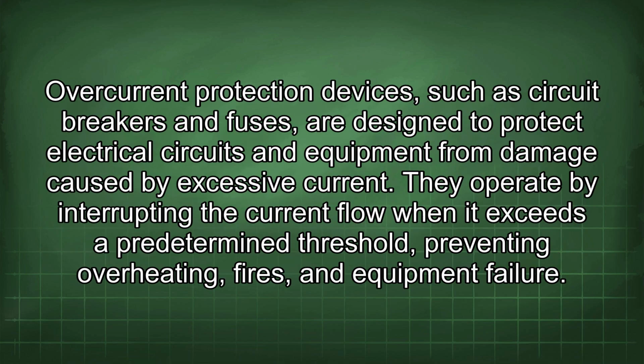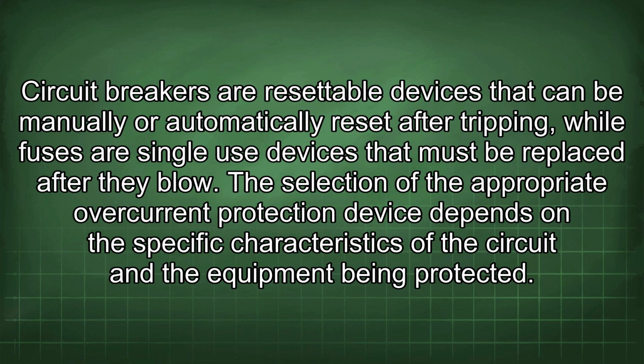Overcurrent protection devices, such as circuit breakers and fuses, are designed to protect electrical circuits and equipment from damage caused by excessive current. They operate by interrupting the current flow when it exceeds a predetermined threshold, preventing overheating, fires, and equipment failure. Circuit breakers are resettable devices that can be manually or automatically reset after tripping, while fuses are single-use devices that must be replaced after they blow.